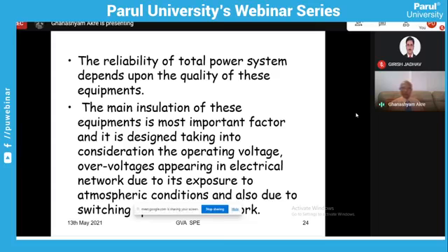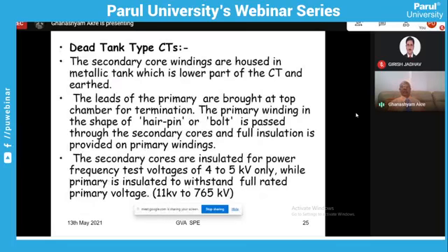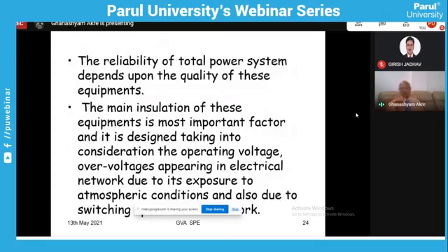And these surges, these impulses from the lightning stroke and these overvoltages which are coming across can damage the equipment connected to it. Hence, the insulation is done selecting all sorts of things, and only after that the insulation is designed. I will just give an example for this insulation, why it is so important.